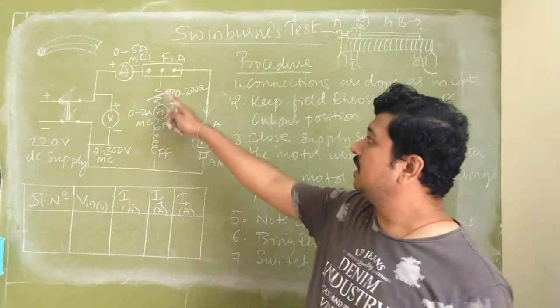But the starter is used to limit the starting current. A large starting current is drawn by any motor. It is not true only with induction or DC, it is true with synchronous motor also, because a synchronous motor is always started as an induction motor, then run as a synchronous motor. Any motor when started will draw a large amount of current because it has to overcome its moment of inertia to supply the starting torque. Starting torque is always larger than running torque.